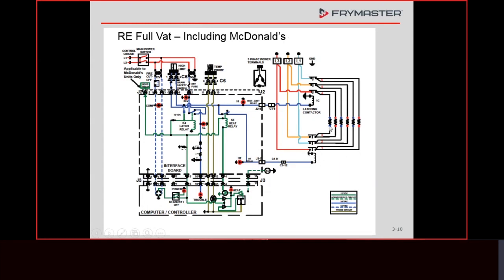It's not that uncommon. It's more uncommon now than it used to be, but for whatever reason, and maybe it's because I was working on electric fryers so much when we were doing a retrofit kit years ago. But yeah, if you take the panels off the back and get one of these white wires that come off the elements pinched, okay, we just provided a ground. We've got voltage, we've got a load, we've got a ground. That's a circuit. Okay, it's going to start to heat. That one pinched wire could cause this fryer to heat to the point it'll trip the hot limit.